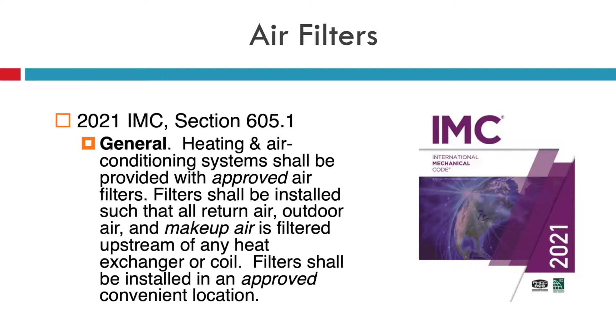When it comes to the 2021 Mechanical Code, in the 2021 IMC in Section 605, the general code reads that heating and air conditioning systems shall be provided with an approved air filter. Those filters shall be installed such that all return air, outdoor air, and makeup air is filtered upstream of any heat exchanger or coil.